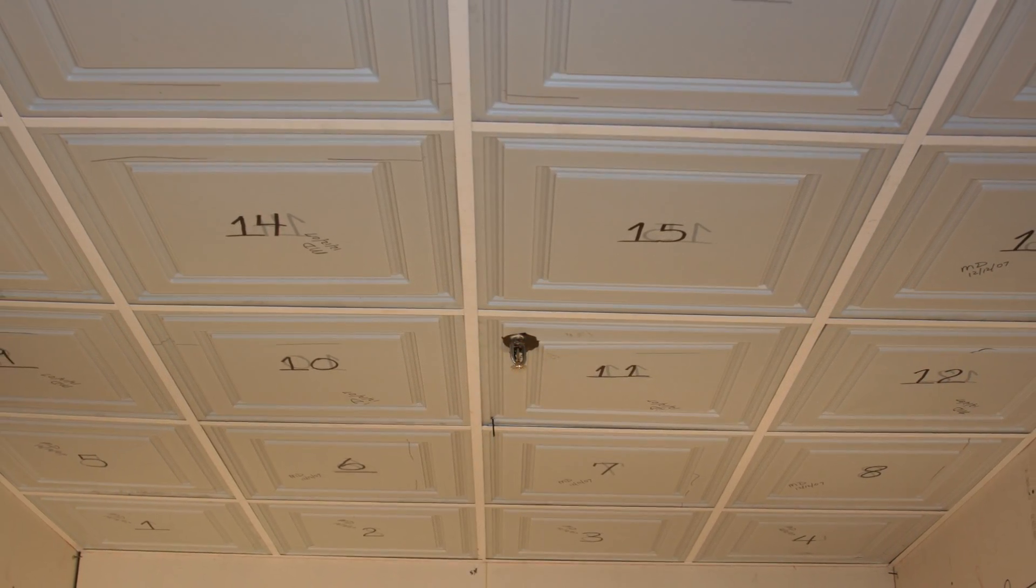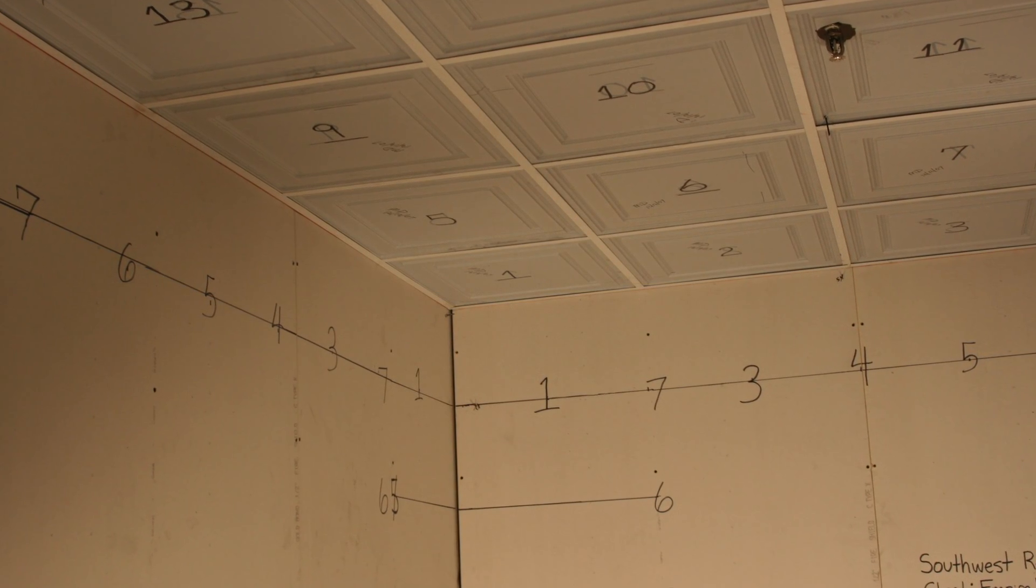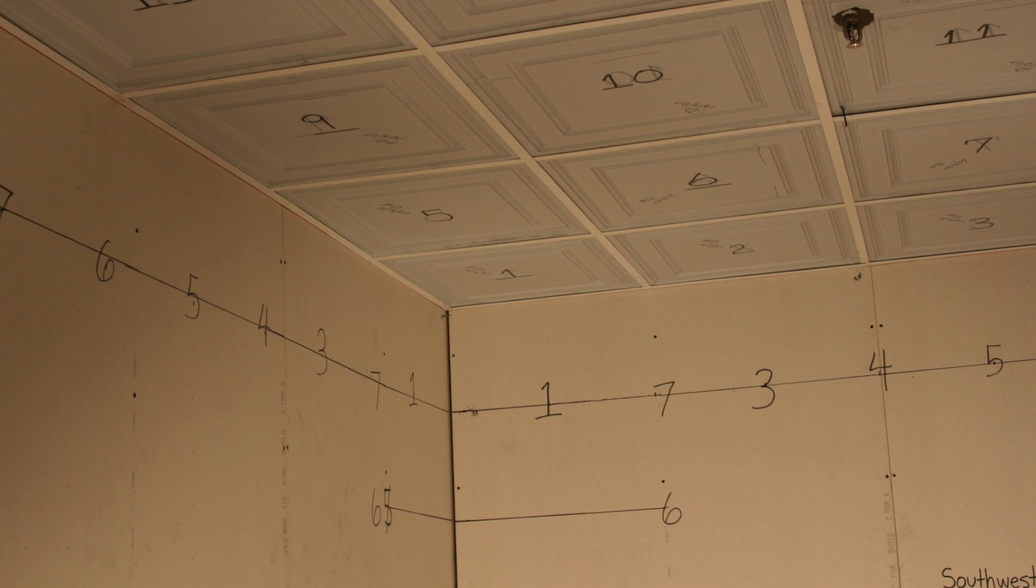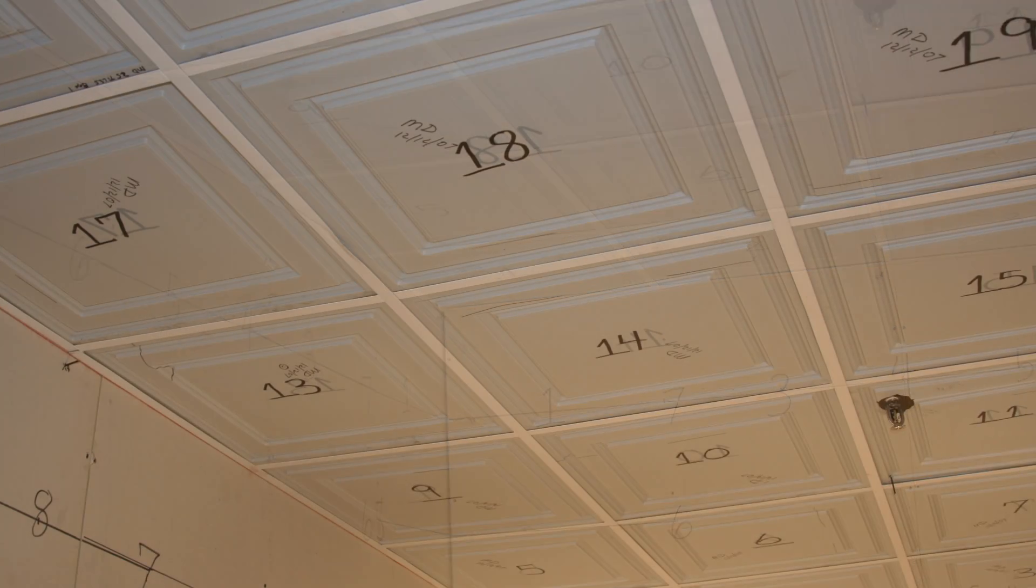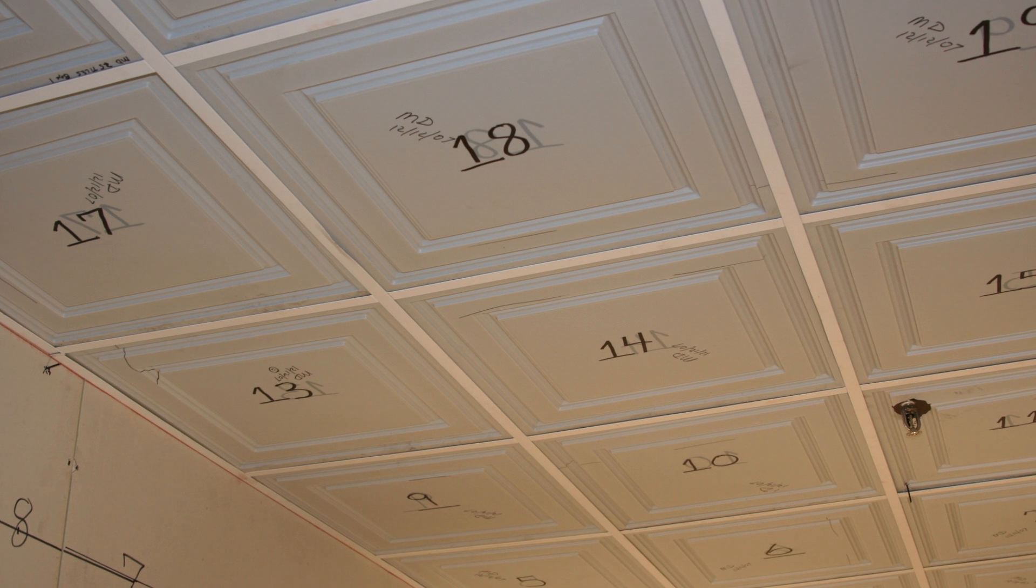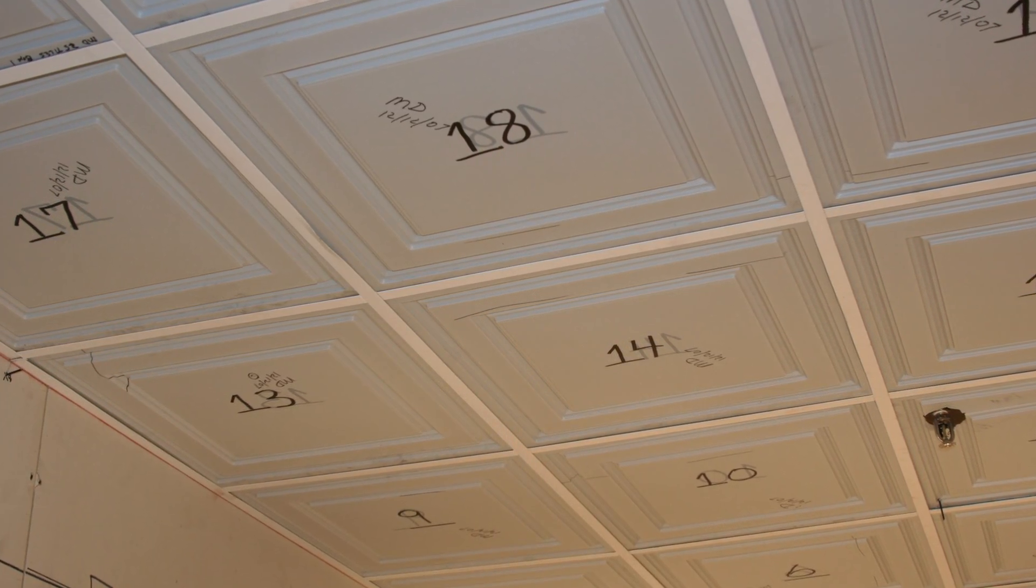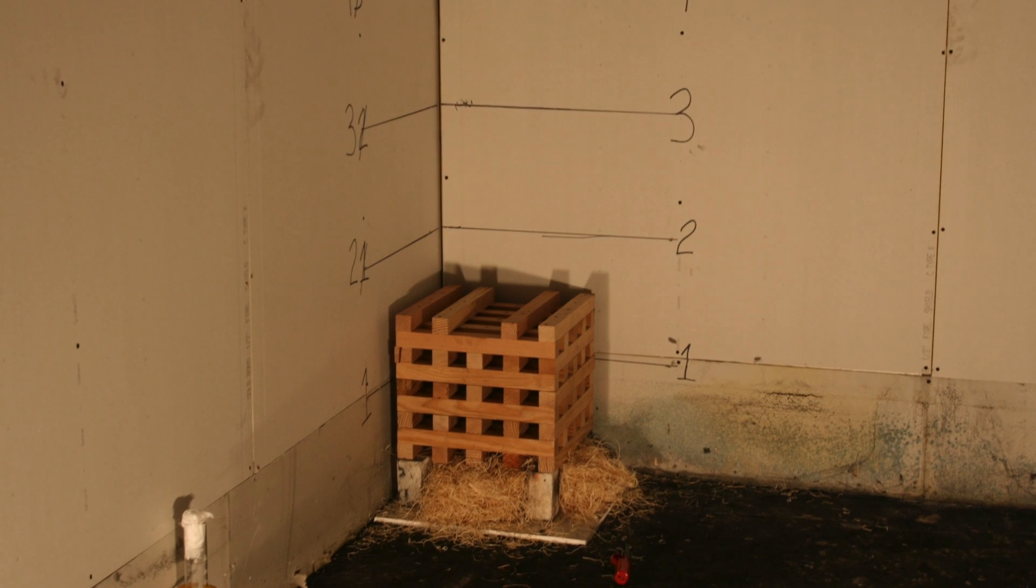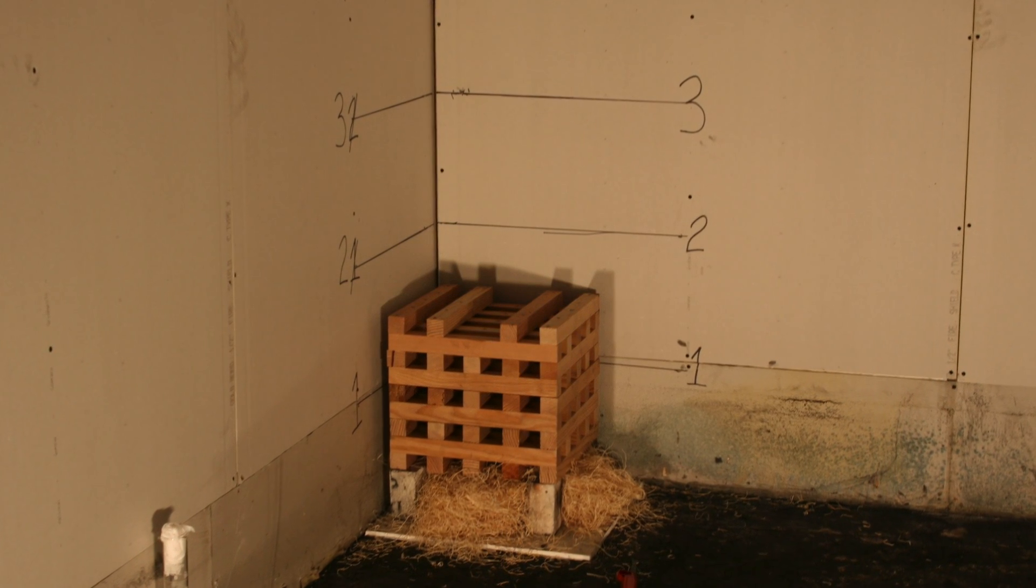An 8 by 12 room with a 9 foot ceiling is constructed as the test chamber. The interior walls and ceilings are covered with half-inch gypsum board. A standard suspended ceiling grid and thermoform ceiling panels are installed one foot below the ceiling. Sprinklers are mounted both penetrating the ceiling panels and above them, and a 30-pound kiln-dried wood crib is placed in one corner as a fire source.